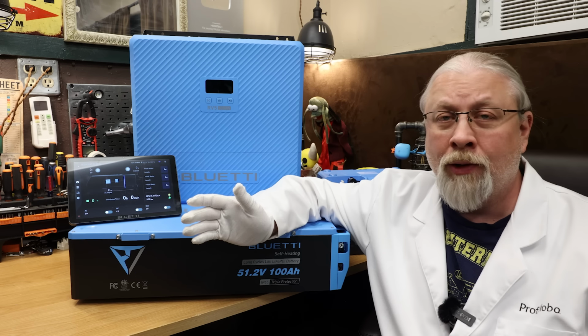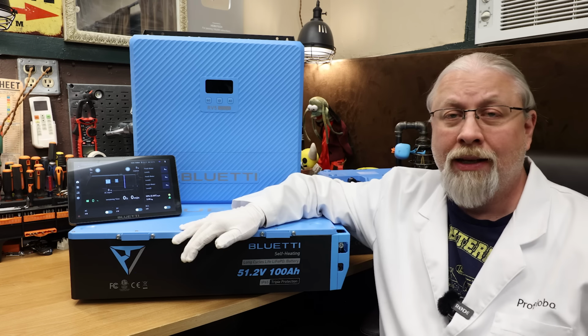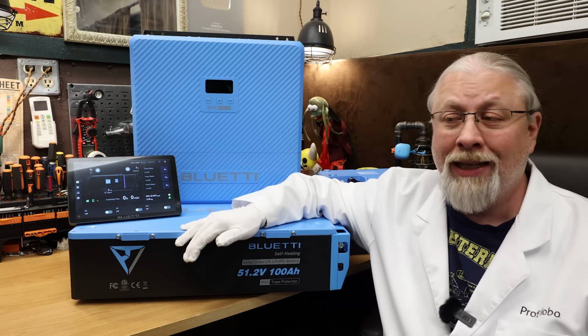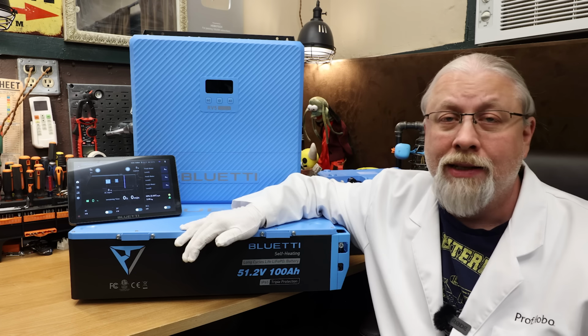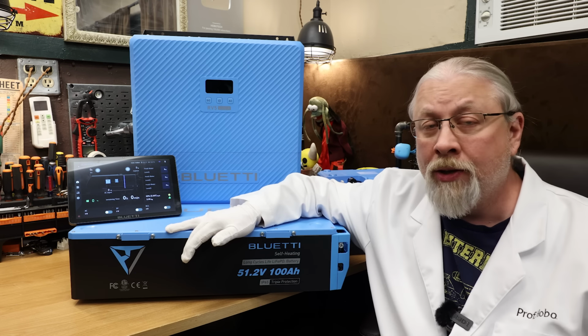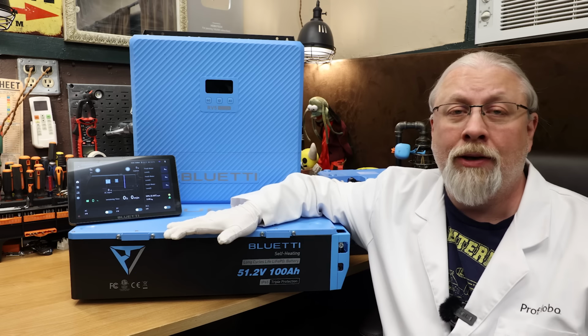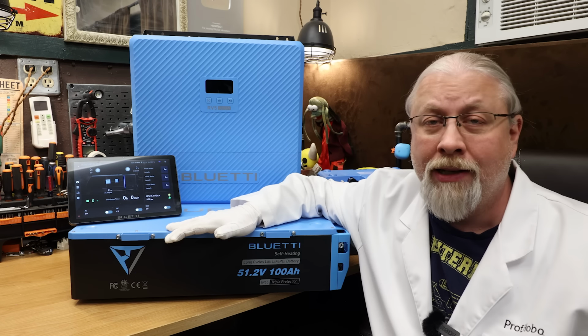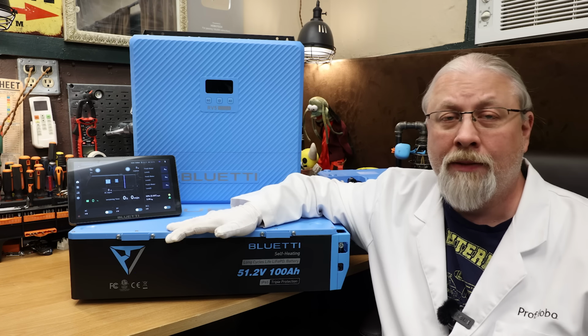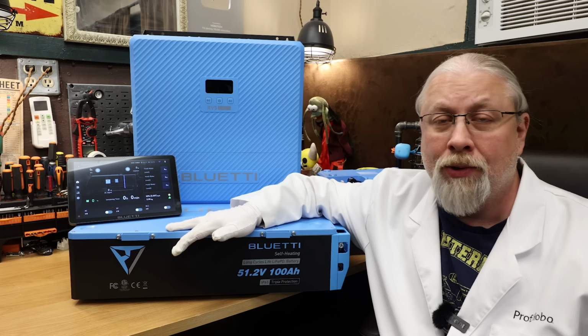Every other 48 volt rack style battery I've ever tested after 2 full cycles has scored at least 100 amp hours in this test. So before anyone tries to blame the Victron shunt, I've tested every battery on this channel with it, and I've even done offline testing with a lab calibrated tester. It's always within about 1.5% accurate.